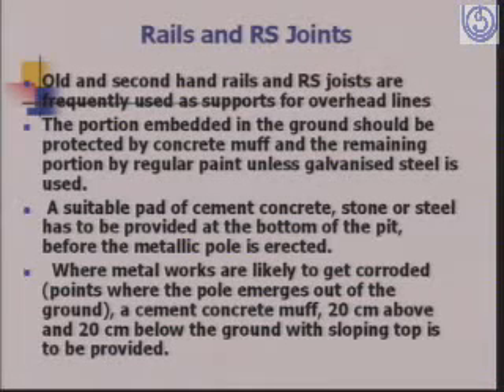Then old rails and RS joists. Old and second-hand rails and RS joists are frequently used as supports for overhead lines. The portion embedded in the ground is covered by concrete muff and the remaining portion by regular paint unless galvanized steel is used. And a suitable pad of cement concrete, stone or steel has to be provided at the bottom of the pit before the metallic pole is erected. Where metal works are likely to get corroded, a cement concrete muff 20 cm above and 20 cm below the ground with sloping top is provided.